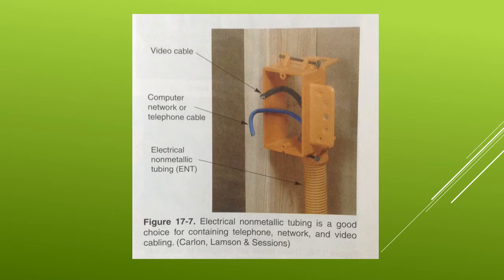Electrical non-metallic tubing. You learned about electrical non-metallic tubing, ENT, in Chapter 4, Wiring Systems. This conduit is typically a corrugated tube with snap-on fittings. Installation requires few tools and limited skills. See figure 17-7. Also, this type of conduit is available in different colors that help identify the purpose for the cabling inside.